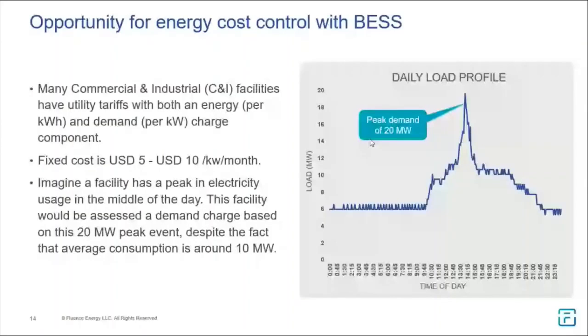In this example, the peak demand went up to about 20 megawatts in a day, whereas the average demand is about 12 megawatts, more like 10, but it goes up to about 12. That one peak of 20 megawatts happened just once during the day, but typically you would go with a connection sized for 20 megawatts.